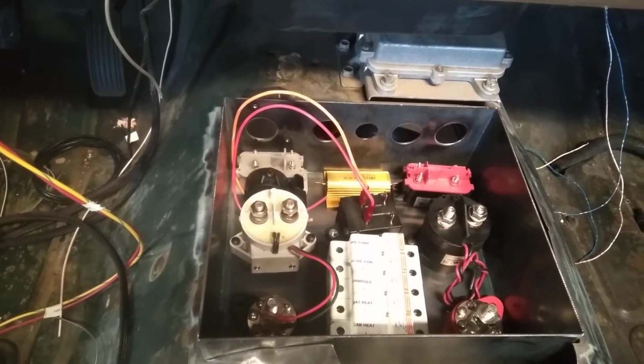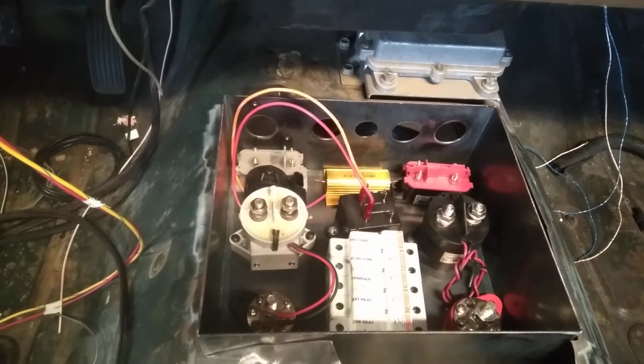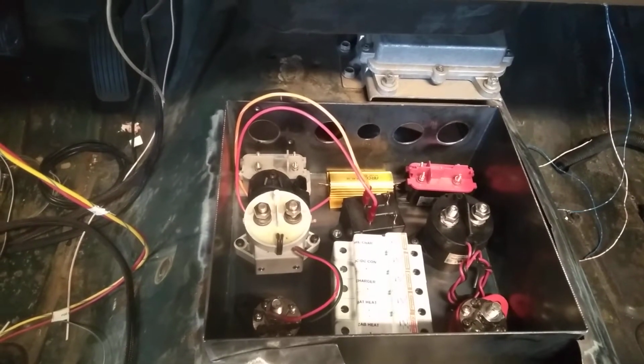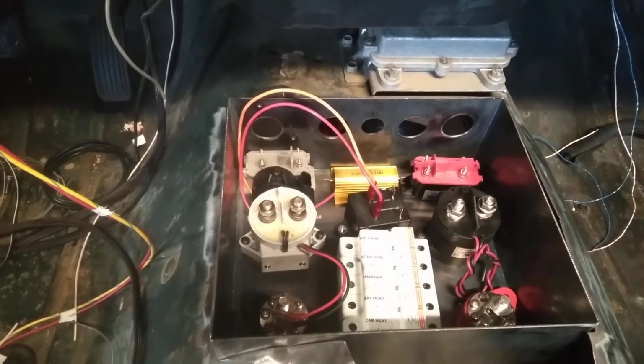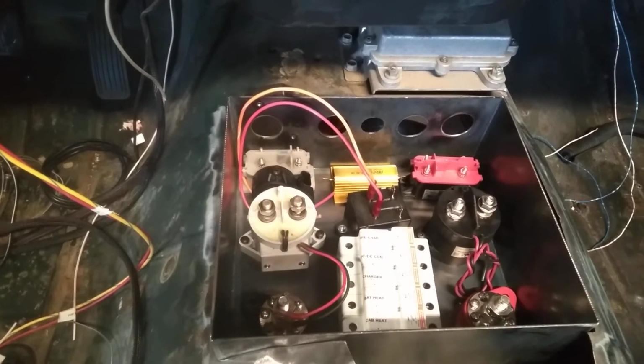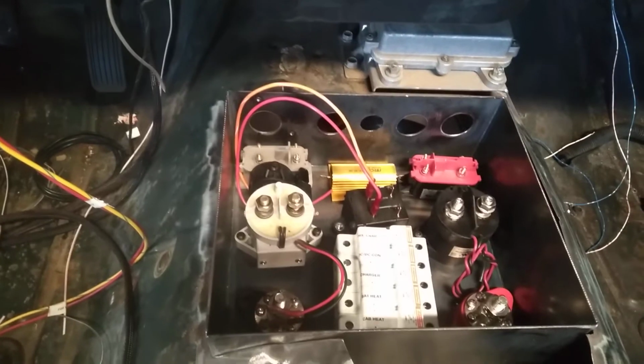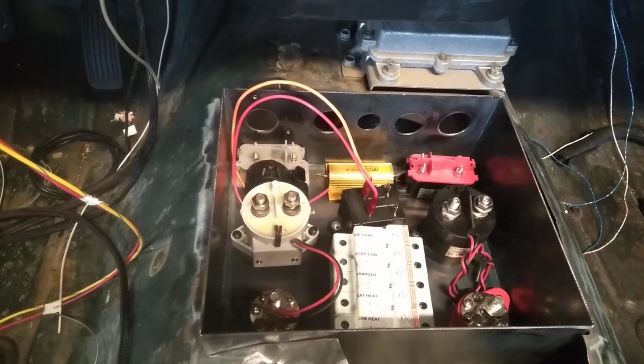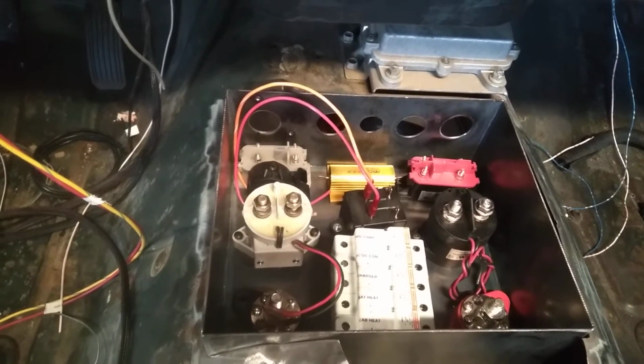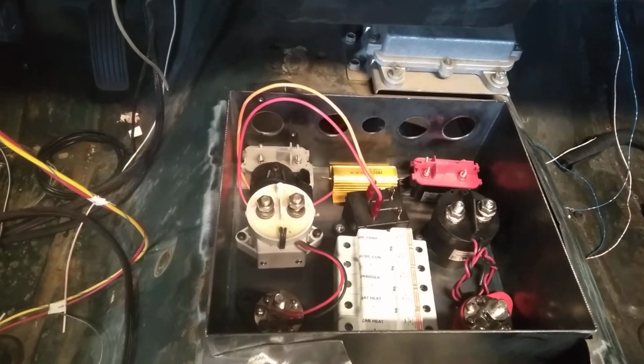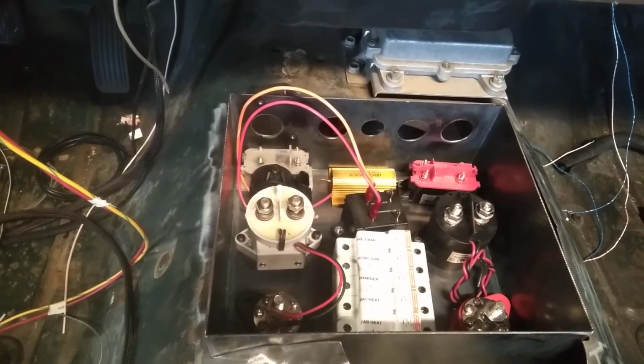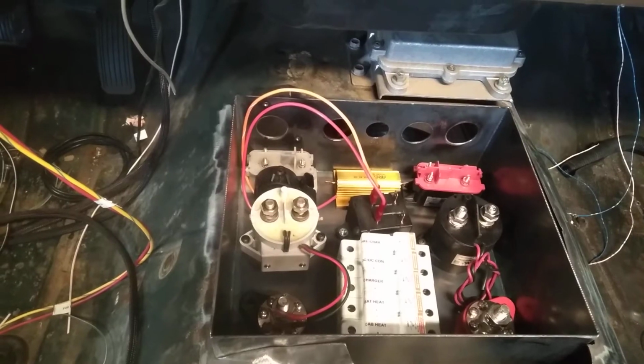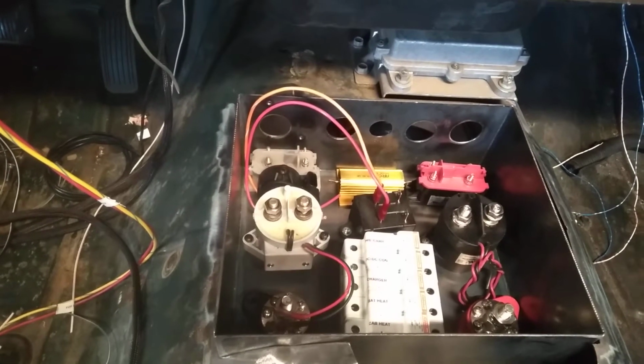The 400 volts DC coming out of the charger will also go through one of those white fuse blocks and go to either the positive battery terminal there on the right, or just straight to the contactor. Probably go with the terminal block, because things just get really crowded on that contactor, and it's not what it's designed for.